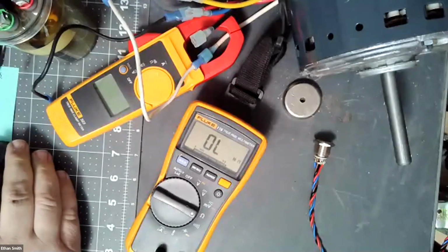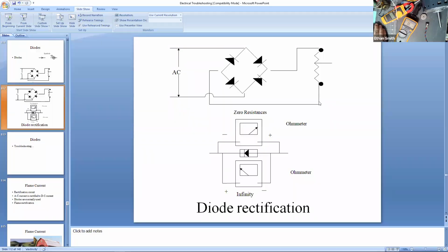So let me pop back into my presentation here. This little device right here is actually a bridge rectifier that comes out of an air conditioner. You'll find this in a 2-step scroll compressor air conditioner. They have found that the little solenoid inside the compressor has a longer lifespan if you run it off a DC voltage versus AC voltage. So they take this little bridge rectifier and convert 24 volts AC into 21 volts DC. They run that solenoid off of DC voltage rather than AC voltage just to make it last longer.